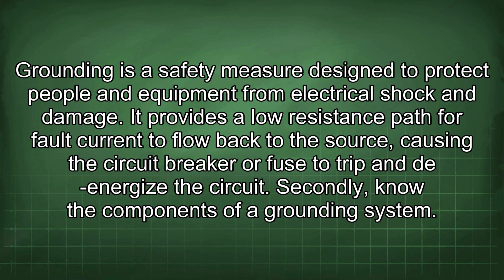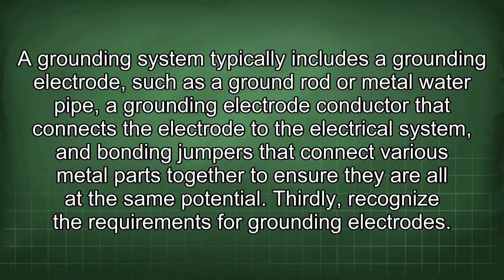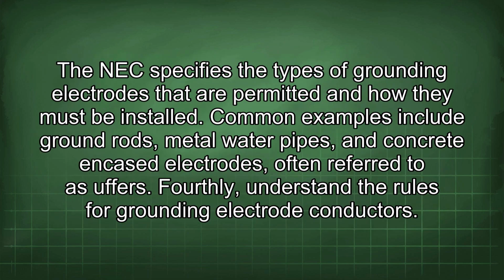Secondly, know the components of a grounding system. A grounding system typically includes a grounding electrode, such as a ground rod or metal water pipe, a grounding electrode conductor that connects the electrode to the electrical system, and bonding jumpers that connect various metal parts together to ensure they are all at the same potential. Thirdly, recognize the requirements for grounding electrodes. The NEC specifies the types of grounding electrodes that are permitted and how they must be installed. Common examples include ground rods, metal water pipes, and concrete encased electrodes, often referred to as Ufers.